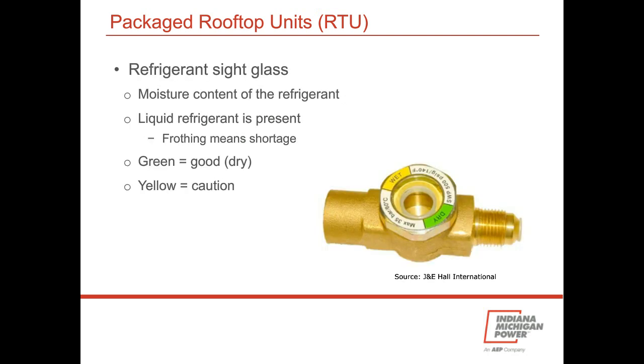Generally speaking, a standard sight glass will be available with an RTU. It has an indicator with a dual function that monitors whether the moisture content of the refrigerant is within an acceptable range, and it indicates whether liquid refrigerant is always present at the expansion component. If the moisture content is okay, the indicator color will be green. You won't have to do any further action. If the indicator color, however, is yellow, that's going to indicate there's a problem with the moisture content of the refrigerant. And frothing in the sight glass would indicate either a shortage of refrigerant or that the refrigerant in the liquid line is not entirely in the liquid state. So it's a nice indicator of what's going on with your refrigerant.